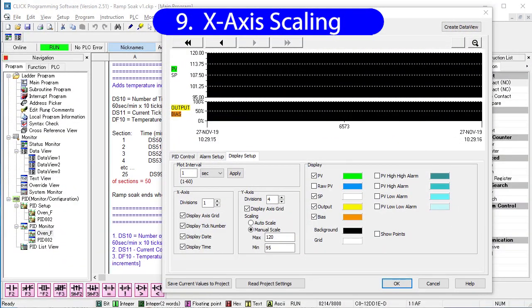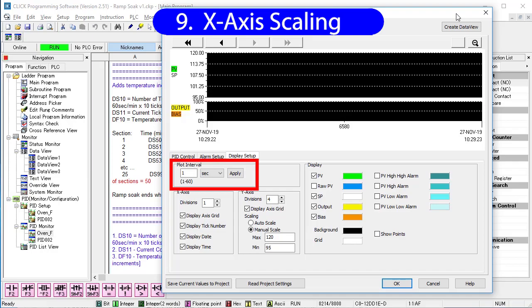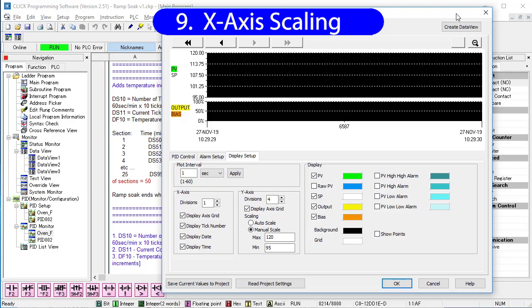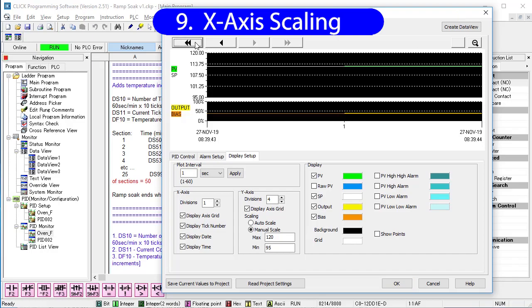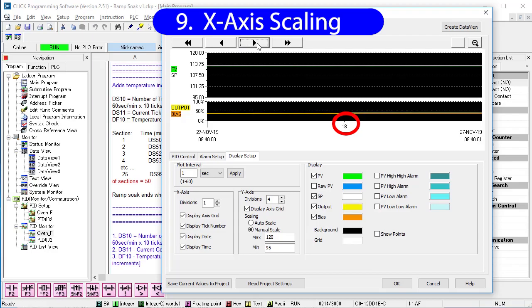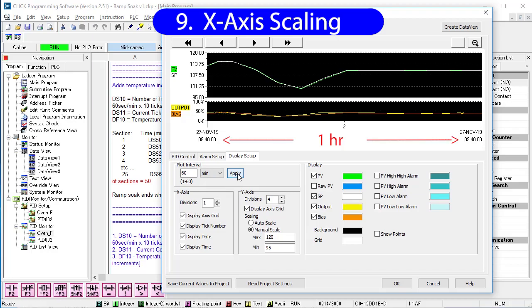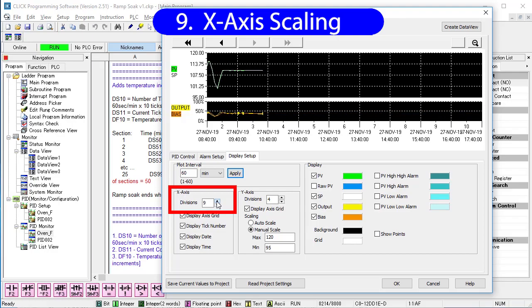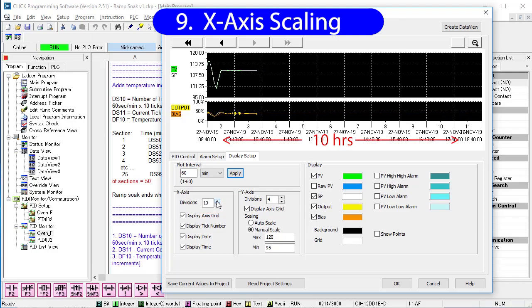The Click PID monitor can display an enormous amount of historical data, so there are several levels of scaling to help manage that. First, there is the plot interval duration. This is a plot interval and it is currently 1 second wide. We are looking at a plot interval that is this many seconds after I started the PID monitor. I can scroll back to the beginning or one interval at a time using these arrow keys. We can increase the duration of each of these intervals up to 60 minutes, so now we are looking at an hour of recorded data. You can also show up to 10 of these intervals at the same time, so now we are looking at 10 hours of data.